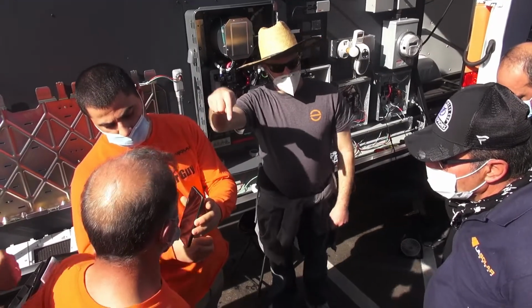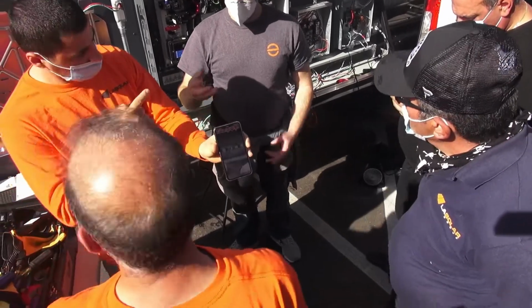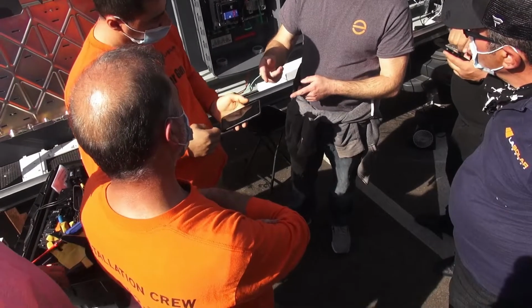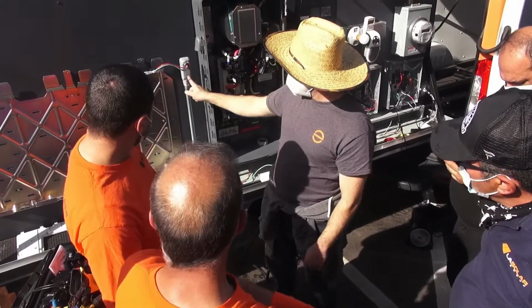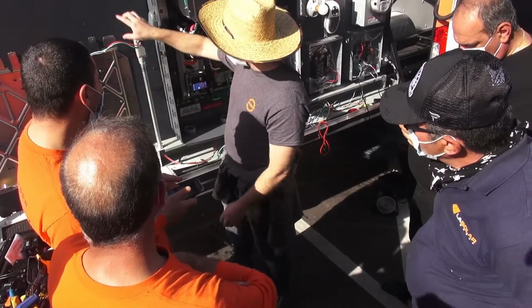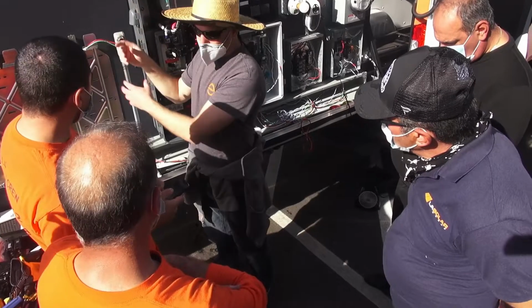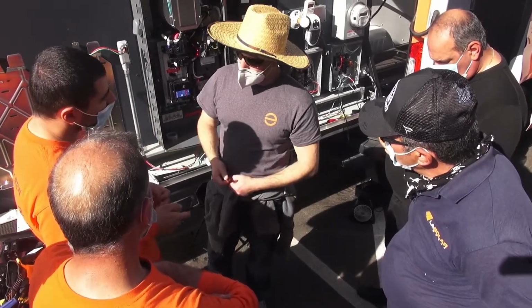So this is a hard scenario because it doesn't make it easy to do that. I've seen people try to splice in here with wire nuts and stuff, or a small sub panel there with breakers. But because of the conduit path, it's not easy.